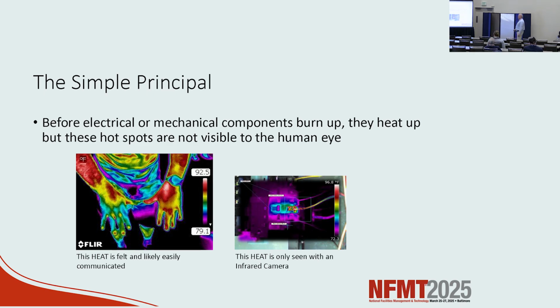So what's the difference between what we feel and what we can see? When we can feel it, we know how to respond - mommy, my hand hurts, can you fix it? But who can see the problem outside of the label I put on it? Can anybody see the problem there? You'll get up there and say, well, I think one of the strands on the stranded line is cut. But thinking and knowing are two different things, and when we put our camera on, it's very clear where the problem is. Now, 80-90% of all faults in thermography are a loose connection.